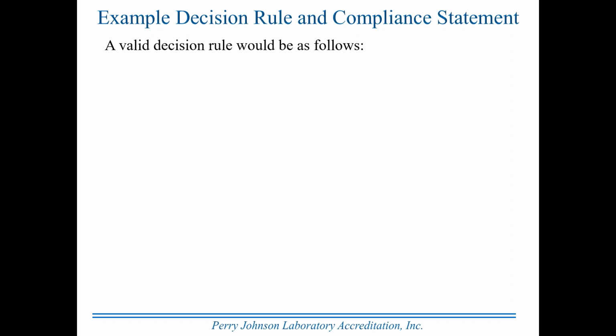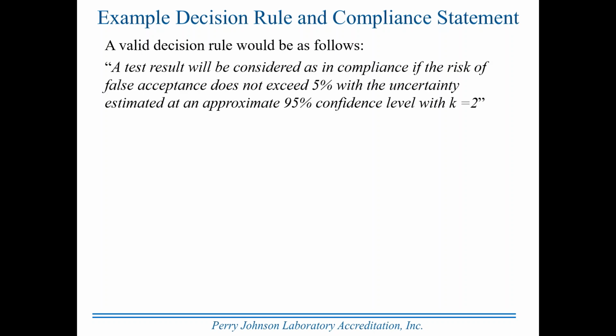Let's look at an example of a decision rule in a compliance statement. A valid decision rule would maybe look as follows. A test result will be considered as in compliance if the risk of false acceptance does not exceed 5% with the uncertainty estimated at an approximate 95% confidence level with K equals 2.